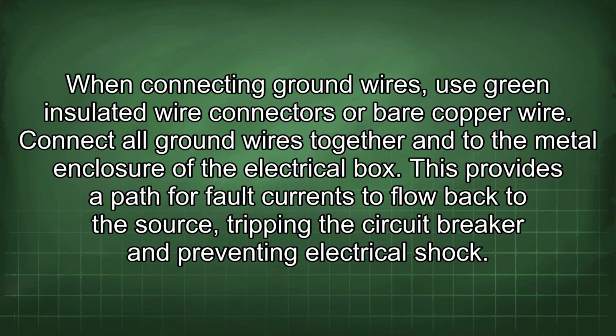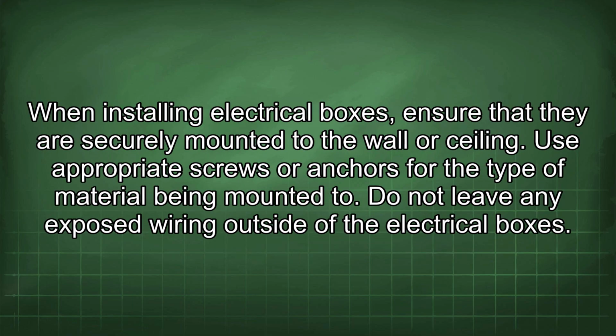When connecting ground wires, use green insulated wire connectors or bare copper wire. Connect all ground wires together and to the metal enclosure of the electrical box. This provides a path for fault currents to flow back to the source, tripping the circuit breaker and preventing electrical shock. When installing electrical boxes, ensure that they are securely mounted to the wall or ceiling. Use appropriate screws or anchors for the type of material being mounted to. Do not leave any exposed wiring outside of the electrical boxes.